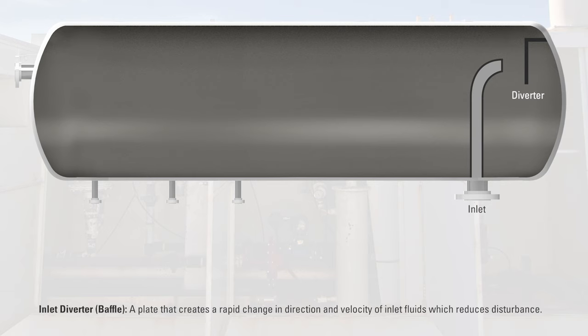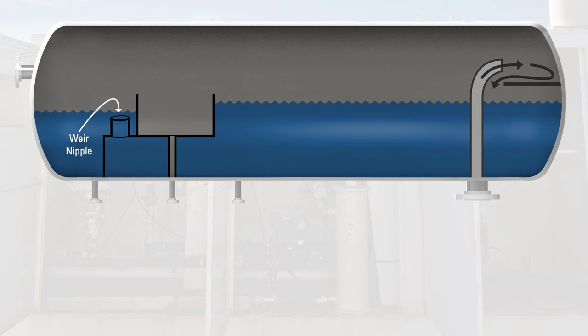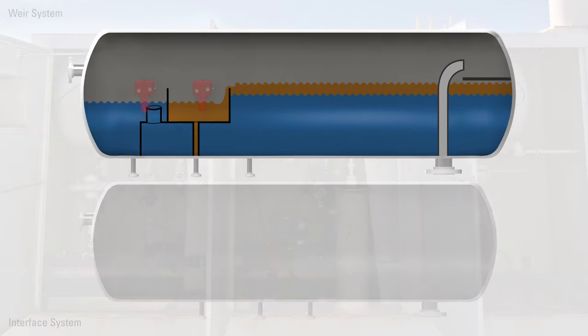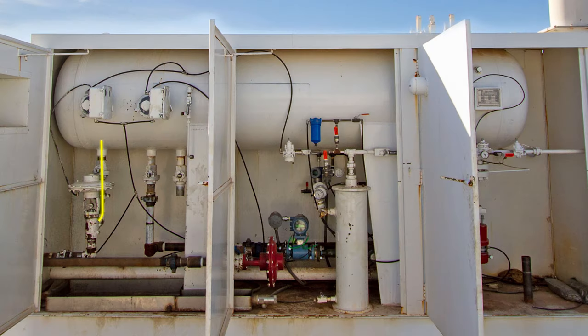There's an inlet diverter inside and the well stream breaks up as it hits against it. Inside this separator are two baffles. Water goes under the first baffle and flows through the weir nipple to establish a water level through the whole length of the separator. The oil then flows over the top of the first baffle into the oil dump chamber. If this were using an interface system, there's only one baffle involved — the water controller on the right establishes an interface which allows the oil to spill over into the oil chamber. In either system, the water is dumped through this outlet and goes downstream for disposal or storage.